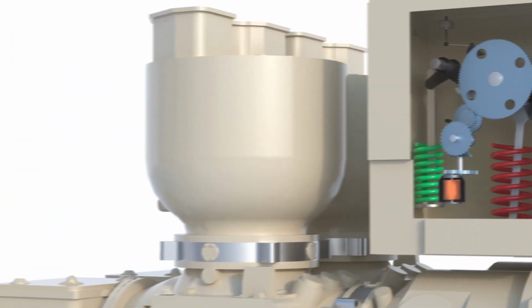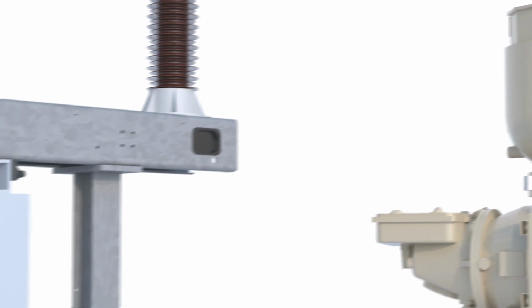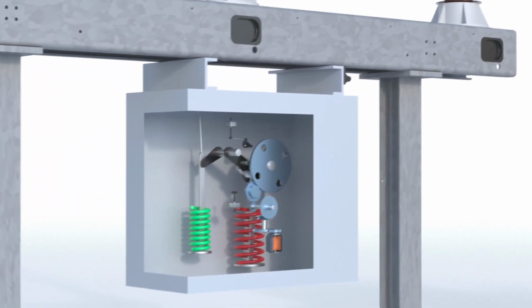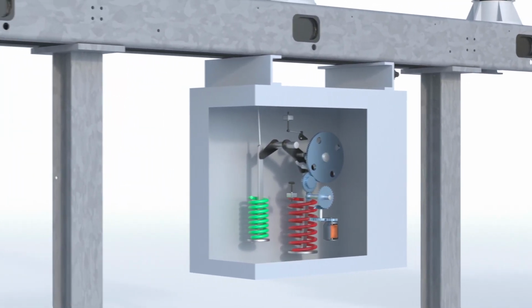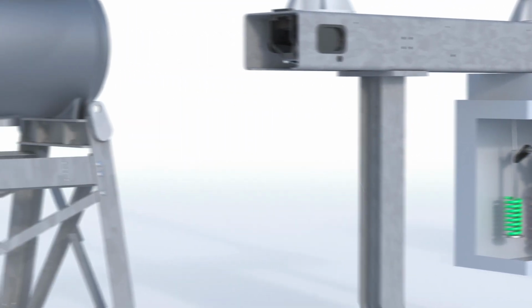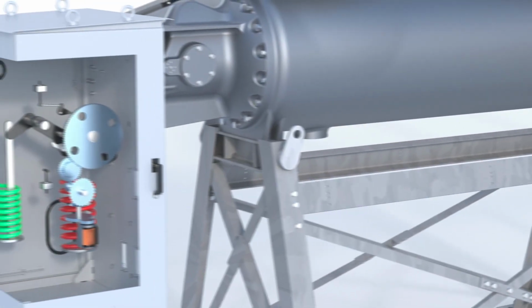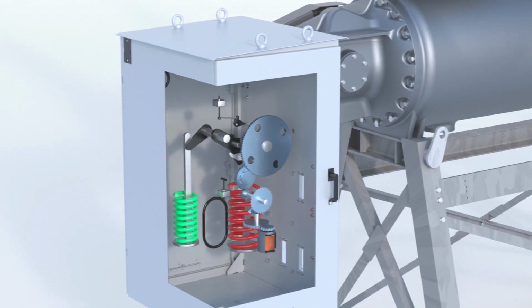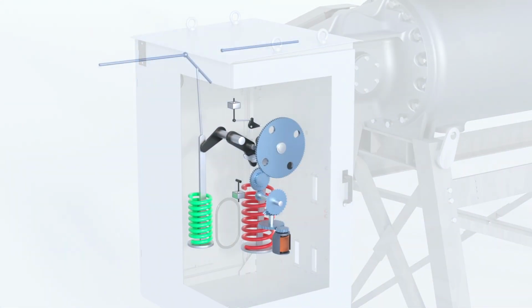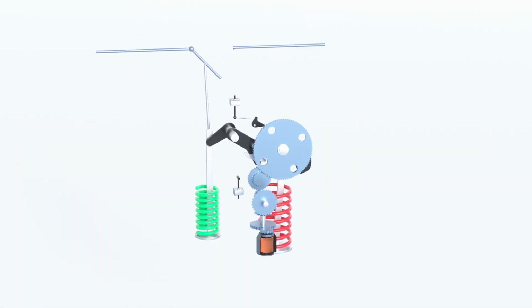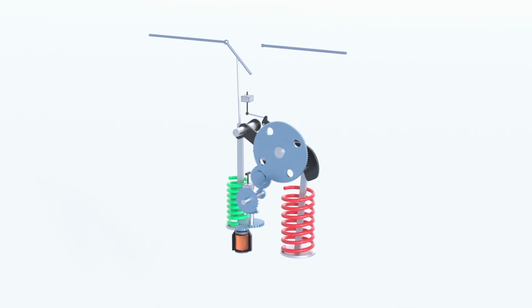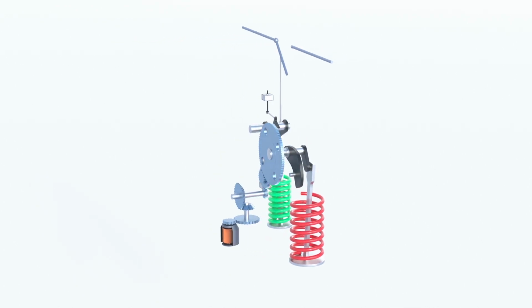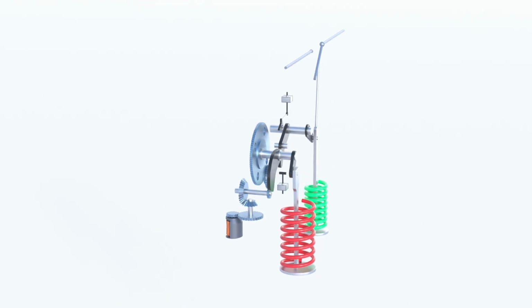The compact and virtually maintenance-free spring drive mechanism provides the force for closing and opening the circuit breaker. The closing and opening springs are located in one single operating mechanism unit. The spring drive mechanism, with its roller bearings and its integrated springs, is completely separated from the gas compartments.